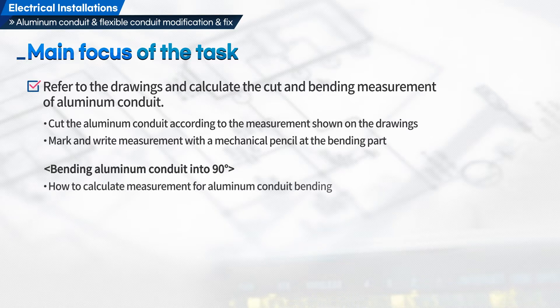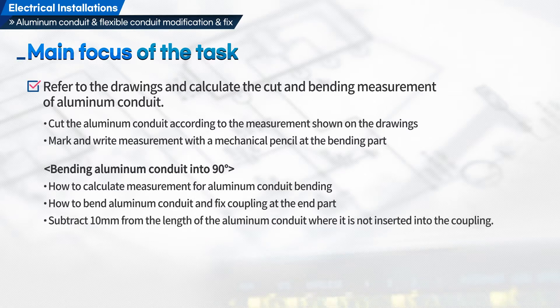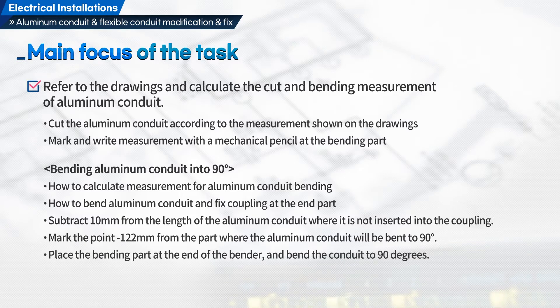How to calculate the measurement for aluminum conduit bending: subtract 10 mm from the length of the aluminum conduit where it is not inserted into the coupling. Mark the point minus 122 mm from the part where the aluminum conduit will be bent to 90 degrees. Place the bending part at the end of the bender and bend the conduit to 90 degrees.